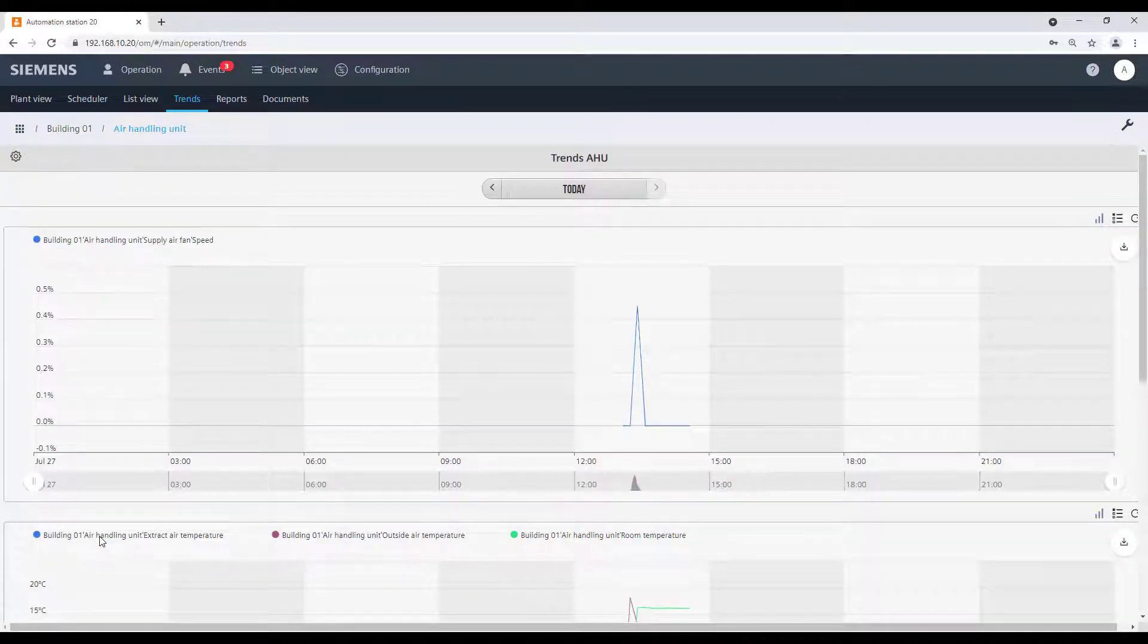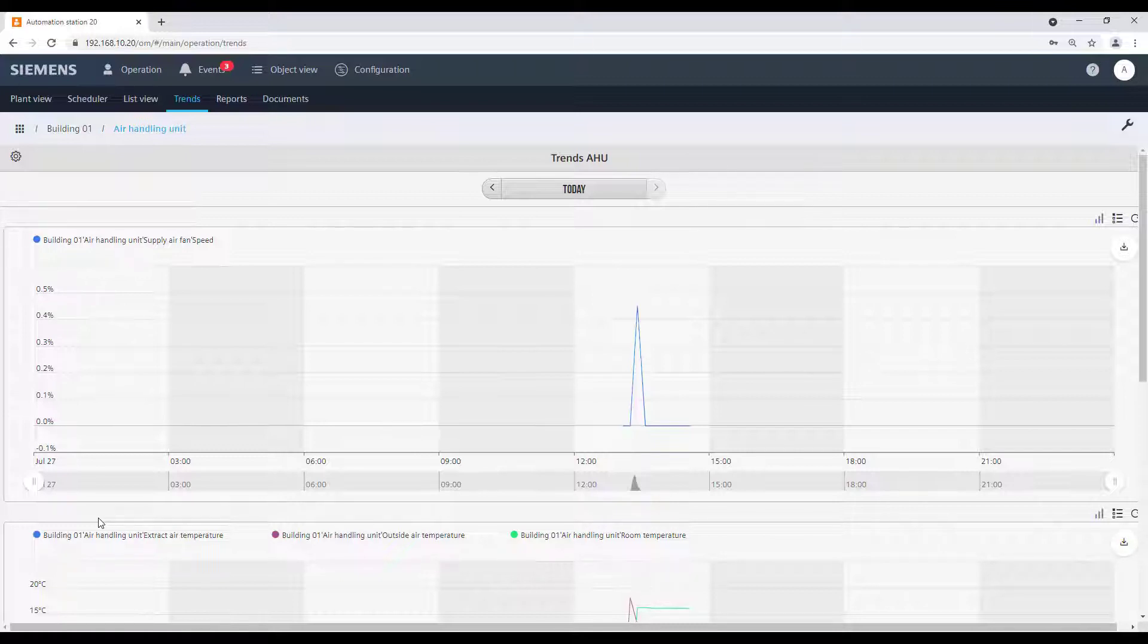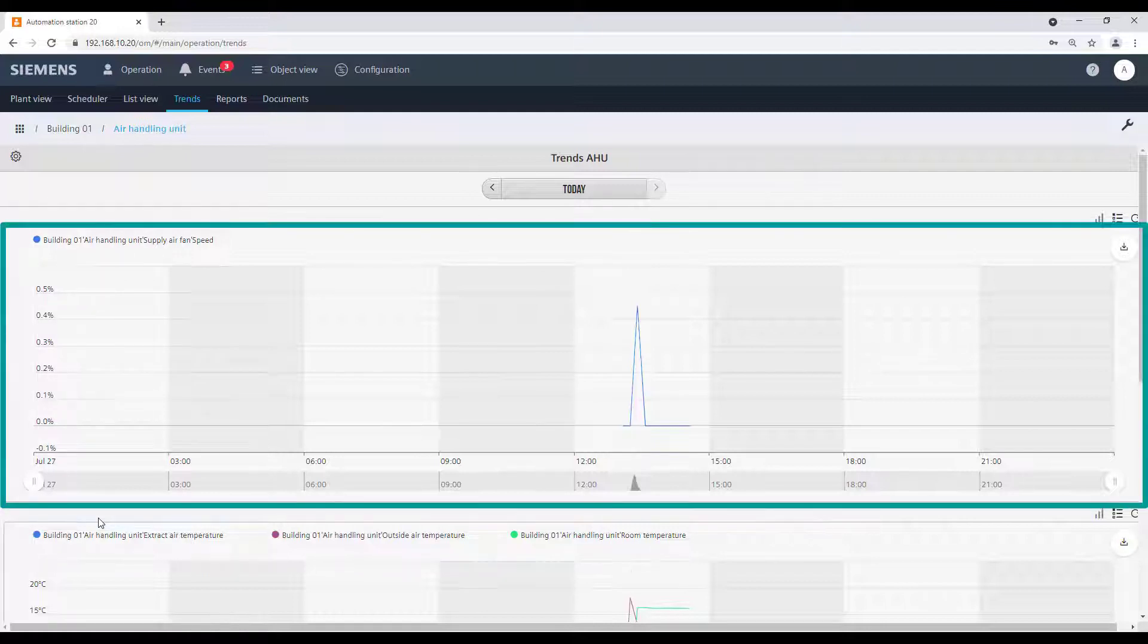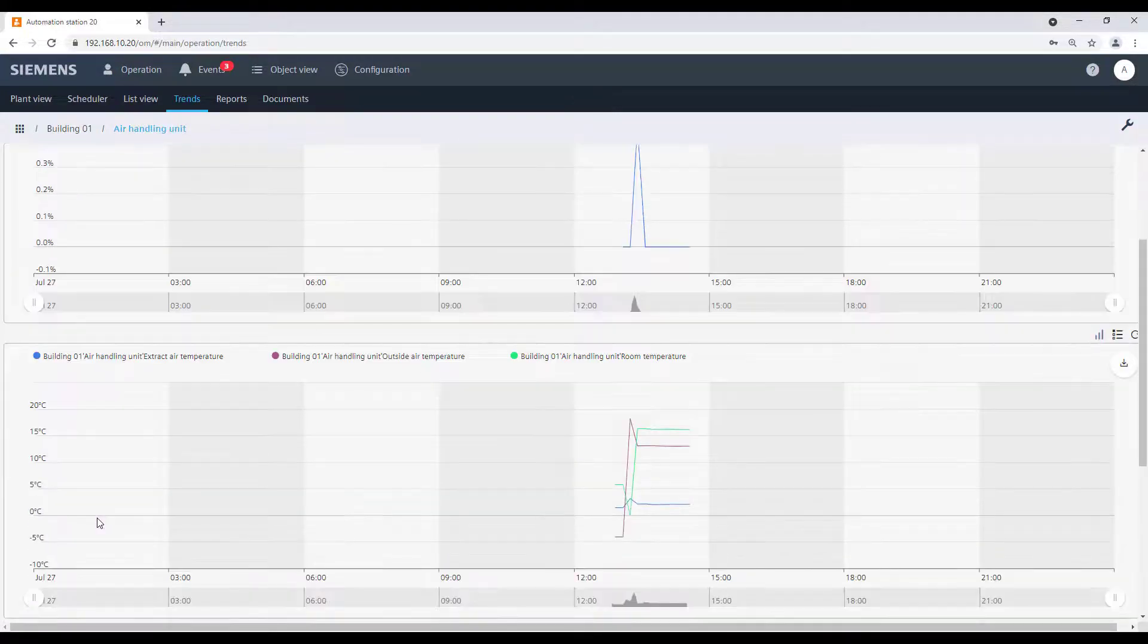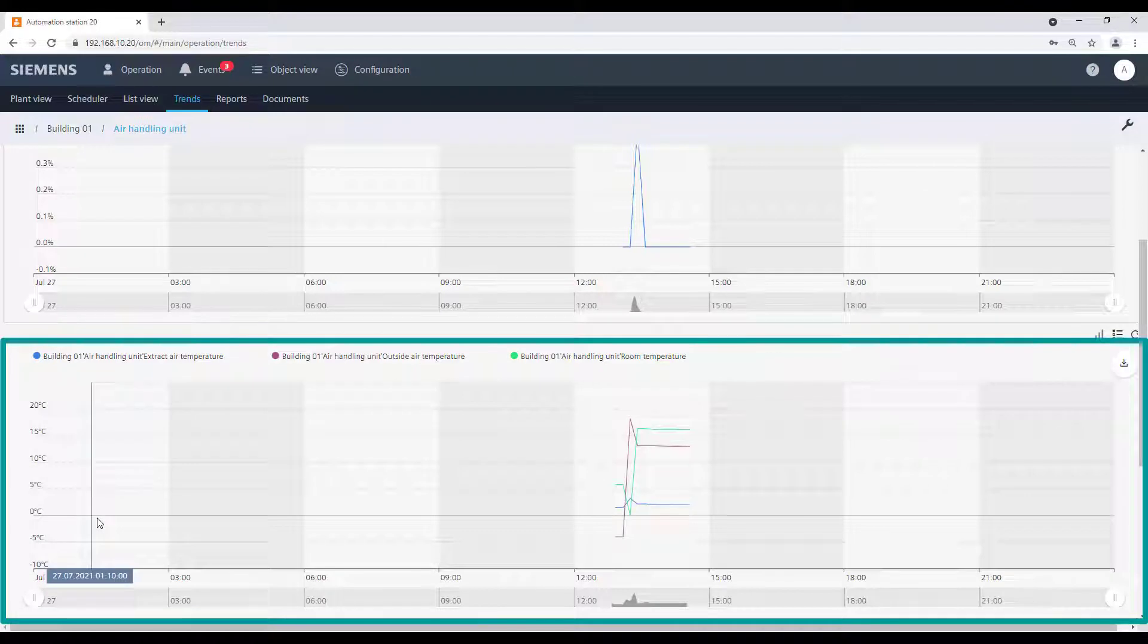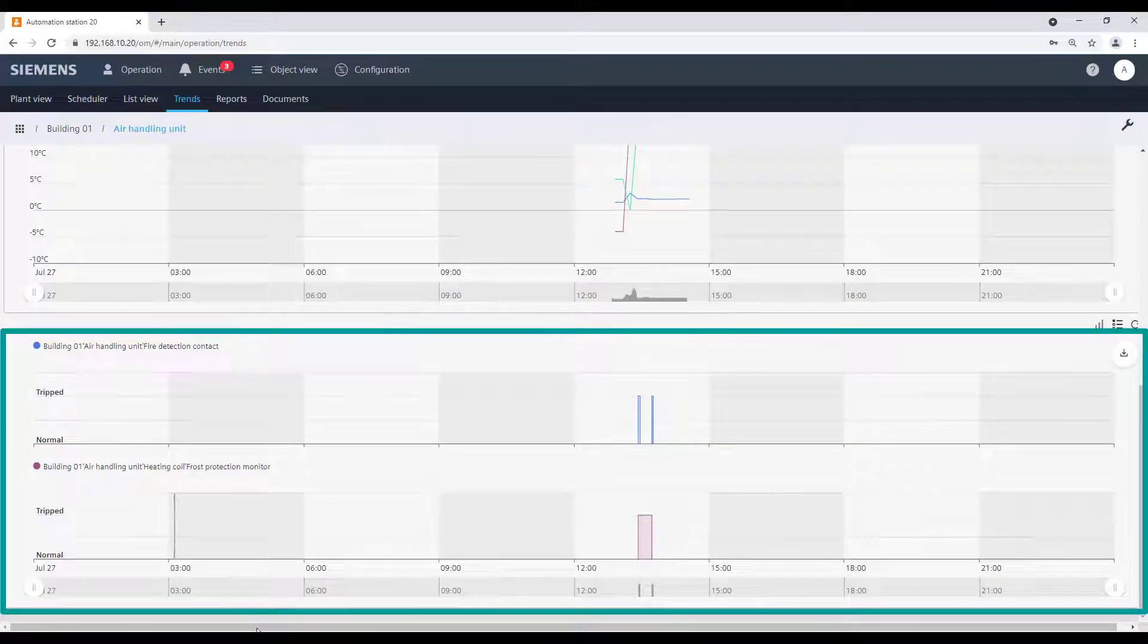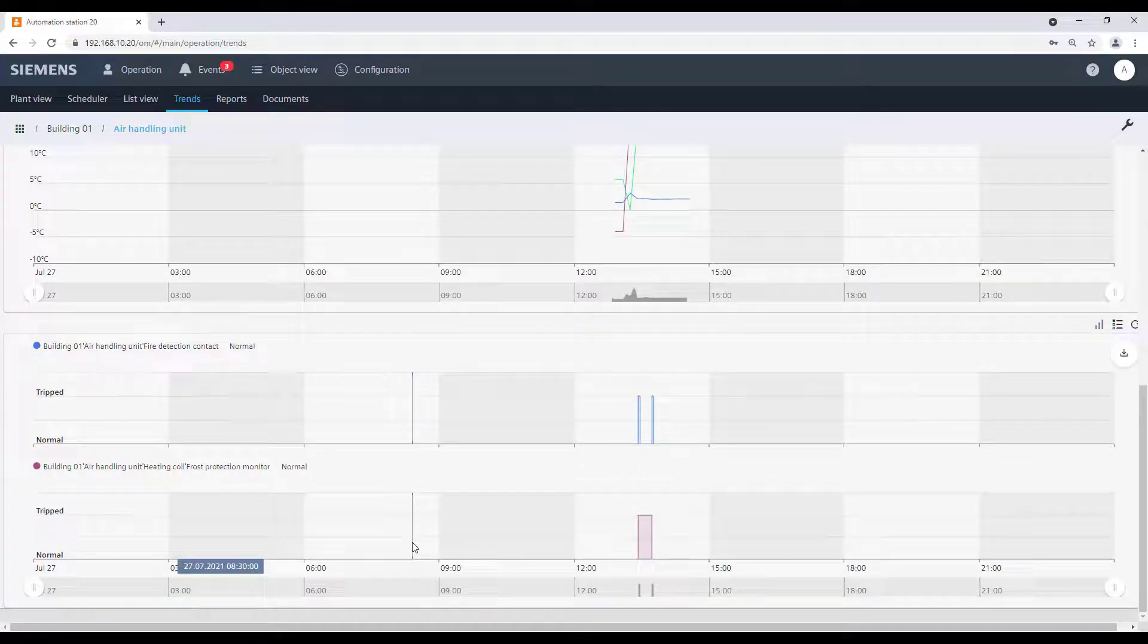The chart view is now displayed. As we can see, it is possible to have one trend graphic with different data types, which are just displayed in different charts. In our example, we have three charts: one for the supply air fan speed, which is an analog output value; one for the air temperatures, which are analog input values; and one for the fire detection contact and frost protection monitor, which are binary input values.